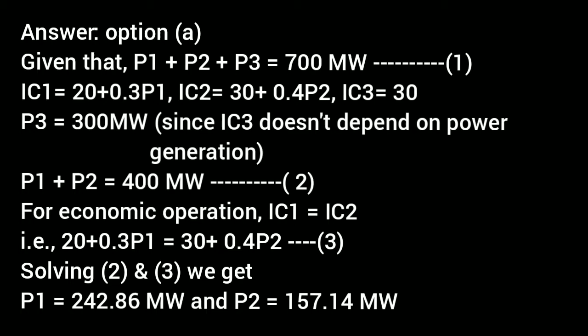So for economic operation, the incremental fuel costs of generating units 1 and 2 will be equal. That is IC1 is equal to IC2. That is 20 plus 0.3 P1 is equal to 30 plus 0.4 P2. Let it be equation 3. By solving equations 2 and 3, we get P1 is equal to 242.86 megawatt and P2 is equal to 157.14 megawatt. So the answer will be option A. That is P1 is equal to 242.86 megawatt, P2 is equal to 157.14 megawatt and P3 is equal to 300 megawatts. So let's move to the next question.